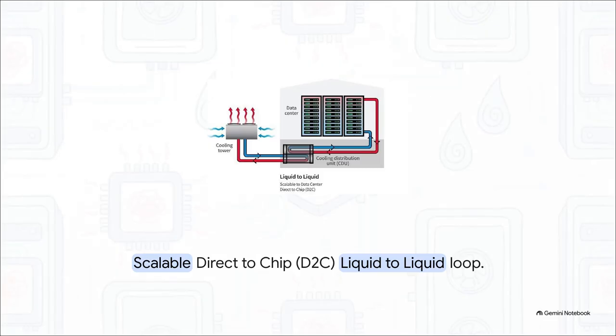The really elegant part about this liquid-to-liquid loop is that the hot liquid is piped completely away from the servers to a cooling distribution unit. The heat is moved entirely out of the server rack and cleanly transferred to the building's external cooling tower. You aren't just blowing hot air around a room anymore. You're surgically extracting heat from the chip and piping it straight outside.